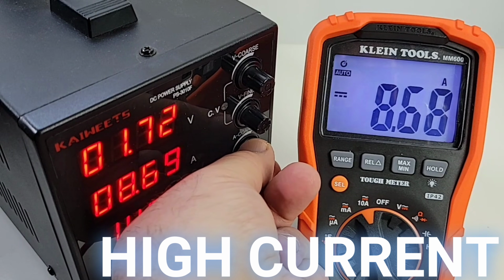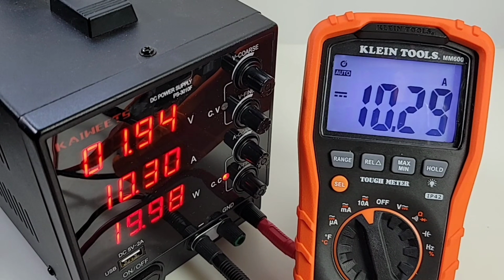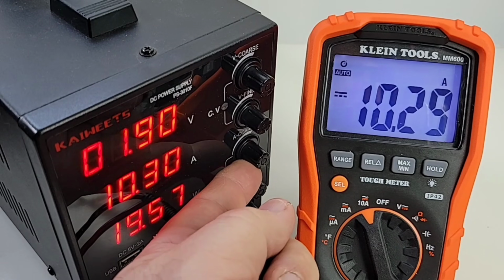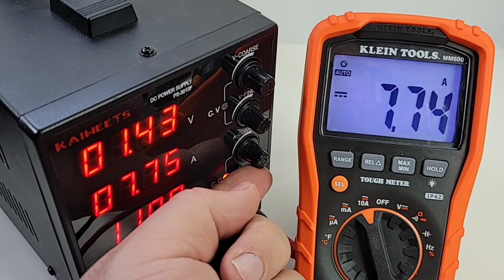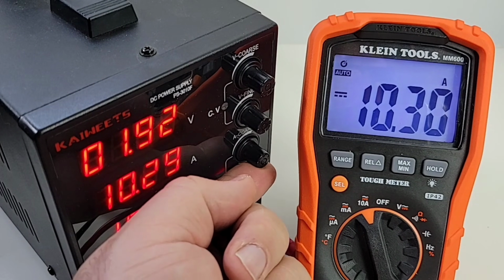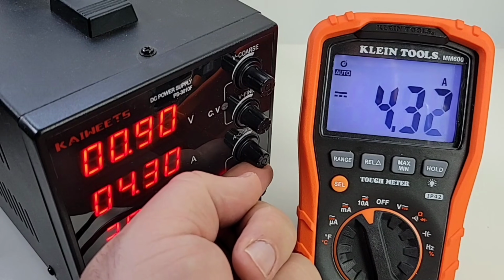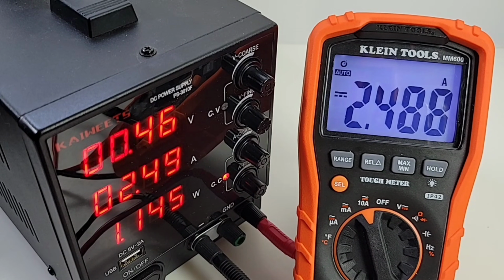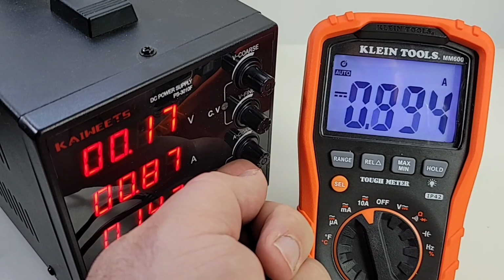We're going to max it out, right past that 10 amp mark. There's the high current alarm at 10.3 amps, showing 10.29. Let's bring it down. So at 10 amps, yeah, the high current alarm kicks in. Good stuff. Now 2.49 amps, 2.488 for the KLEIN, so no problems here with high current.